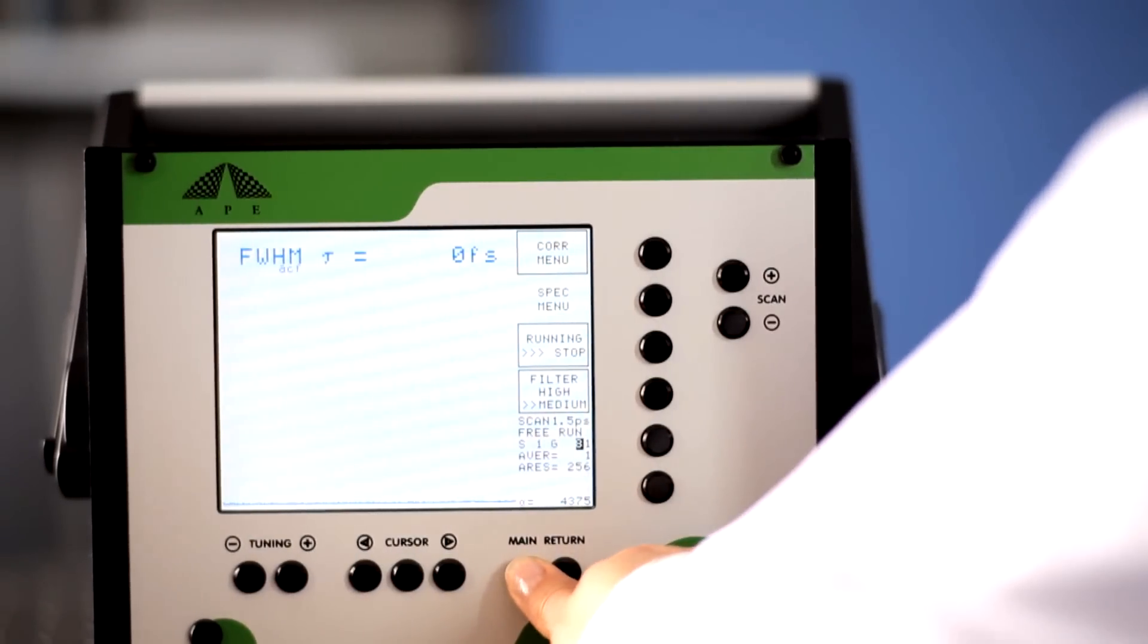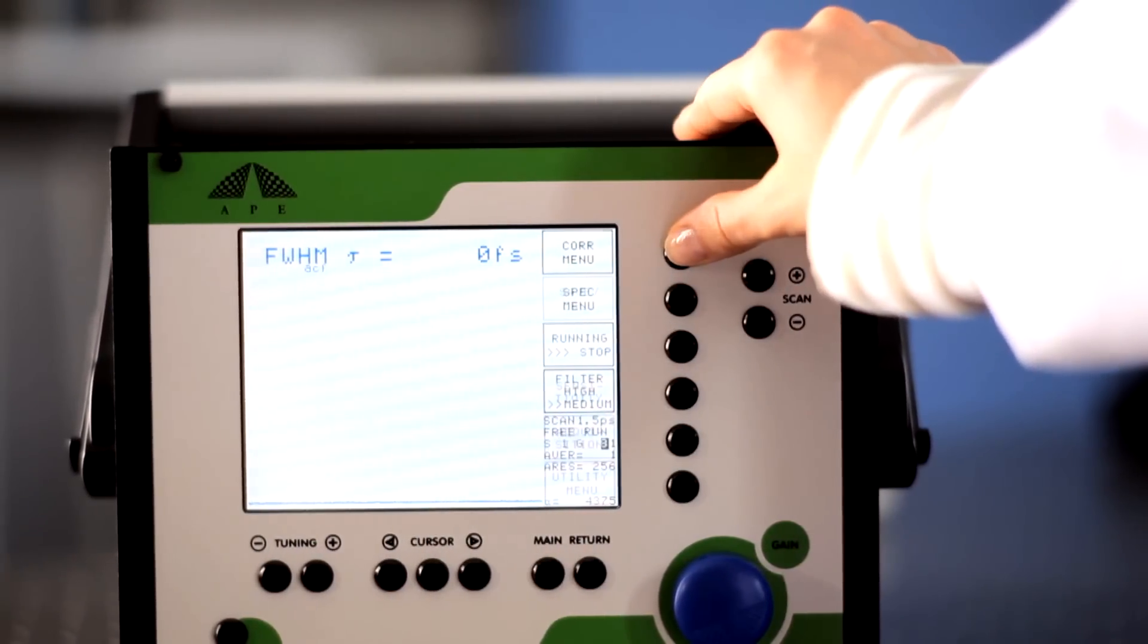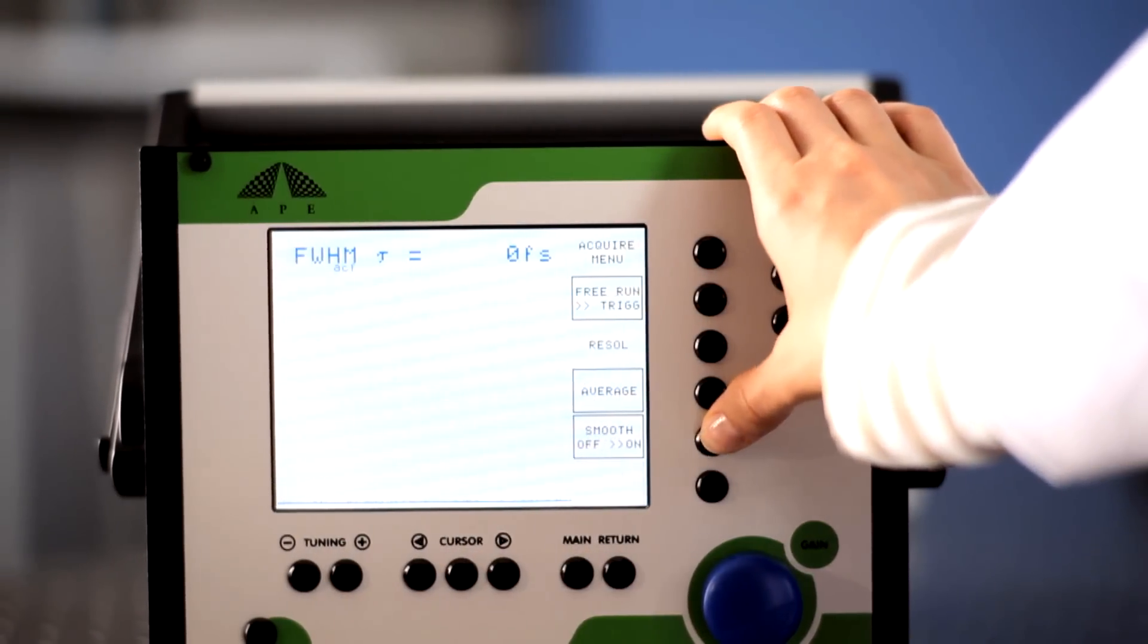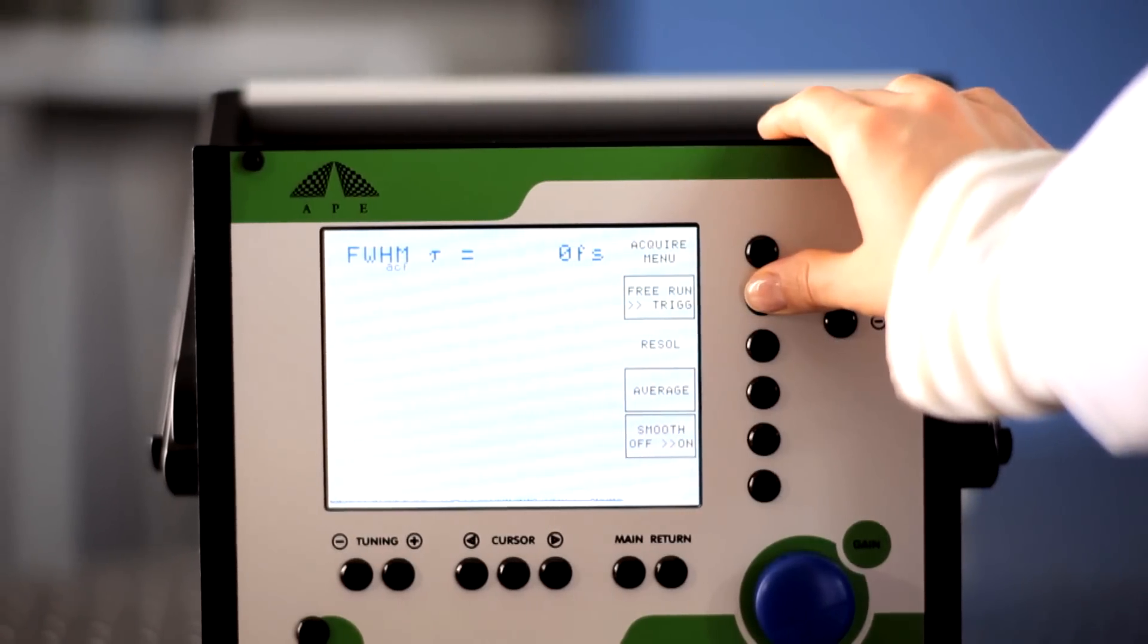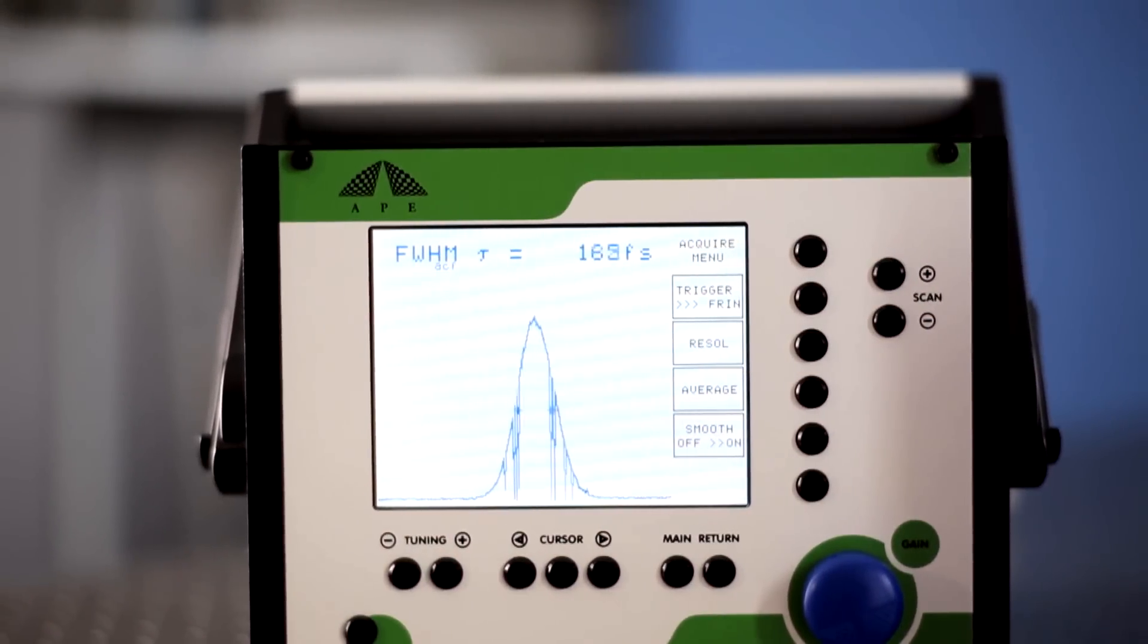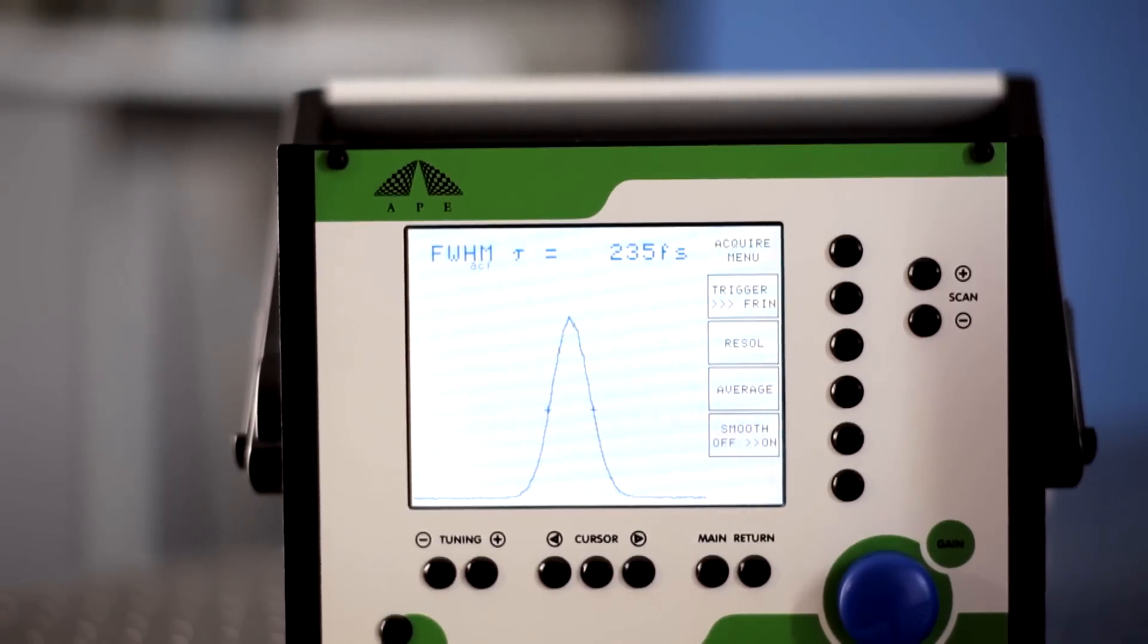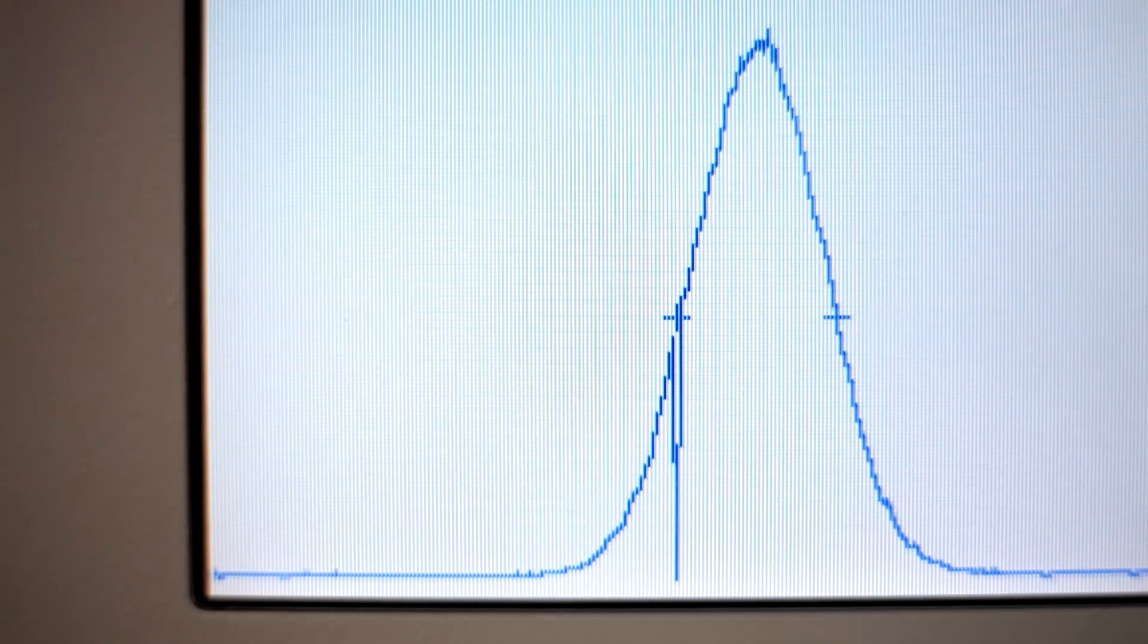Now go to your controller unit and select the main menu. Then select acquisition, and change the setting from free run mode to trigger mode. The display should confirm you're now in trigger mode, so you can be sure your measurements will be totally accurate.